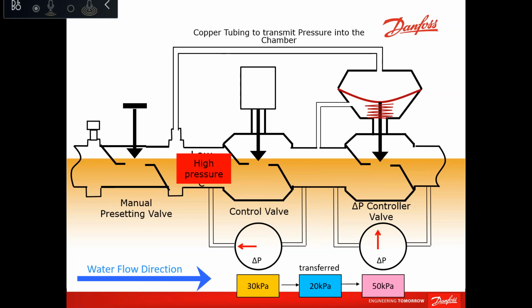Clear? Okay, and if we have a flow rate higher than our maximum flow rate for size DN250, is it okay to use two valves of equal size to cover the flow rate? Yes, two PICVs in parallel will work, subject to the control people knowing how they sequence them. Either they sequence them one valve first and then the second one, or both open and close simultaneously. Yes, it can be done. If you have the space, you can even put three in parallel, no problem, as long as it matches the flow.